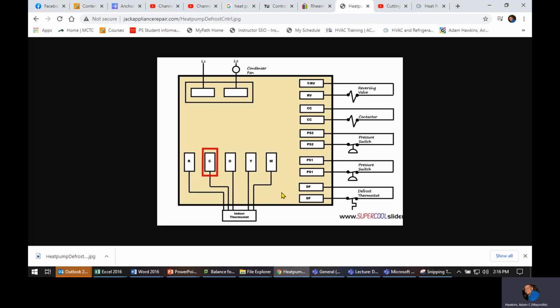So what a defrost board is doing is it's receiving a signal from your stat for all the functions that heat pump's going to have. So a basic heat pump is going to have red, yellow, common, orange or blue, depending on which direction the reversing valve is switching, and then it's going to have W. All right, so without going too far back into the other episodes or into future lessons, I'm just going to stick to the board right now.